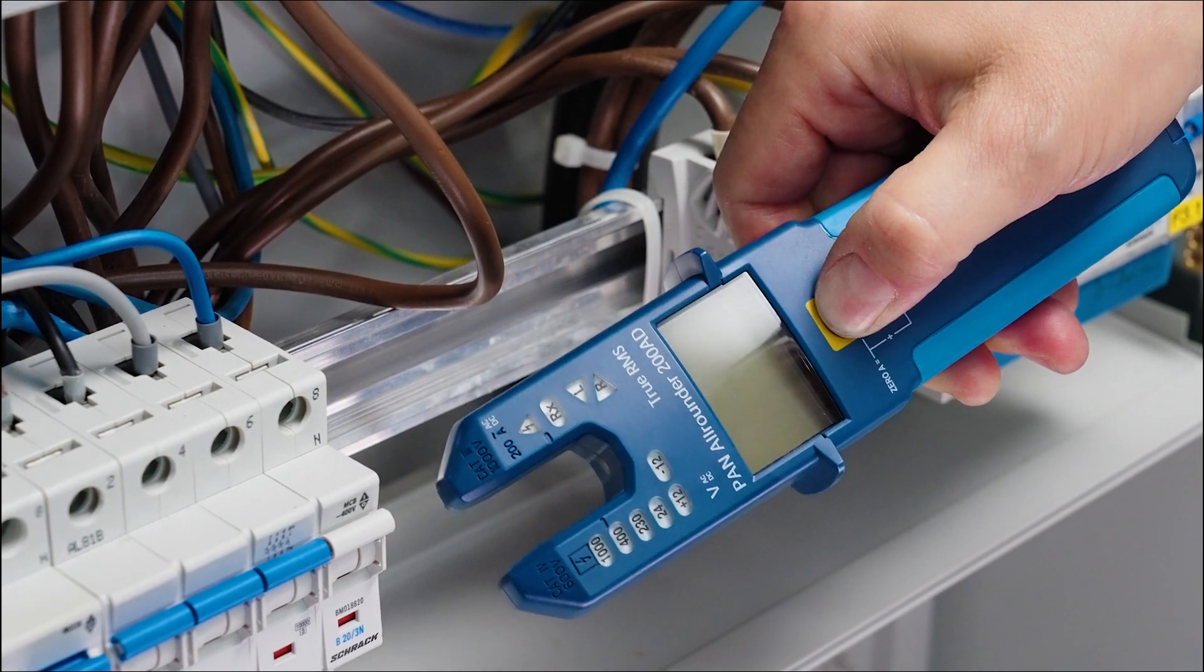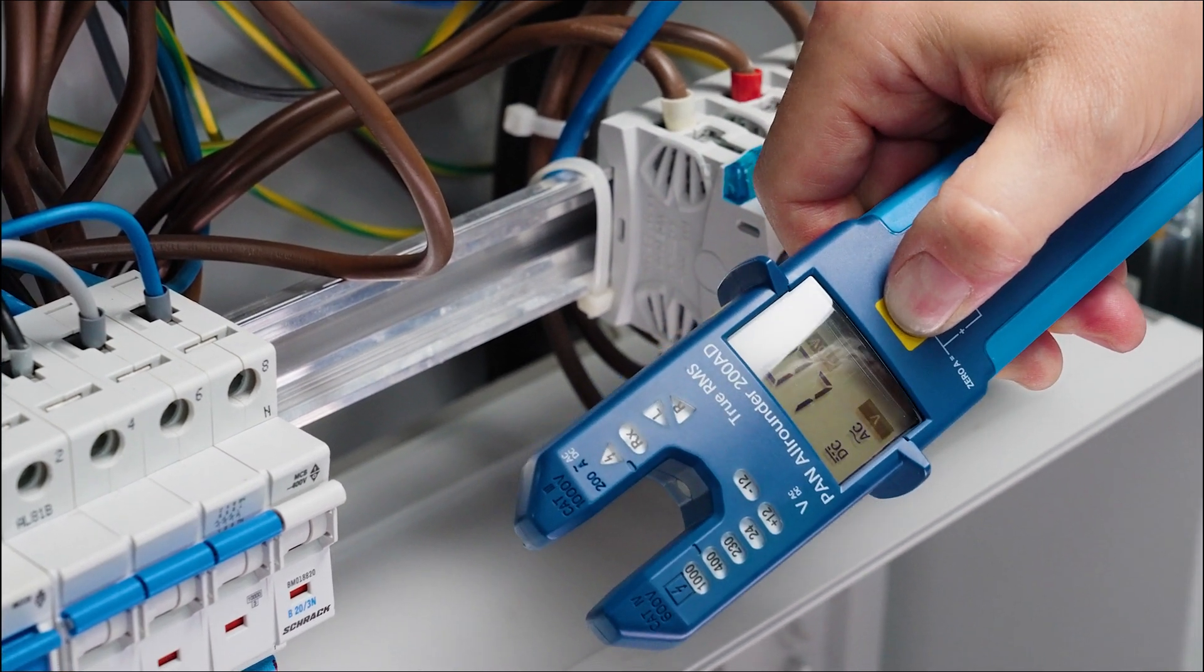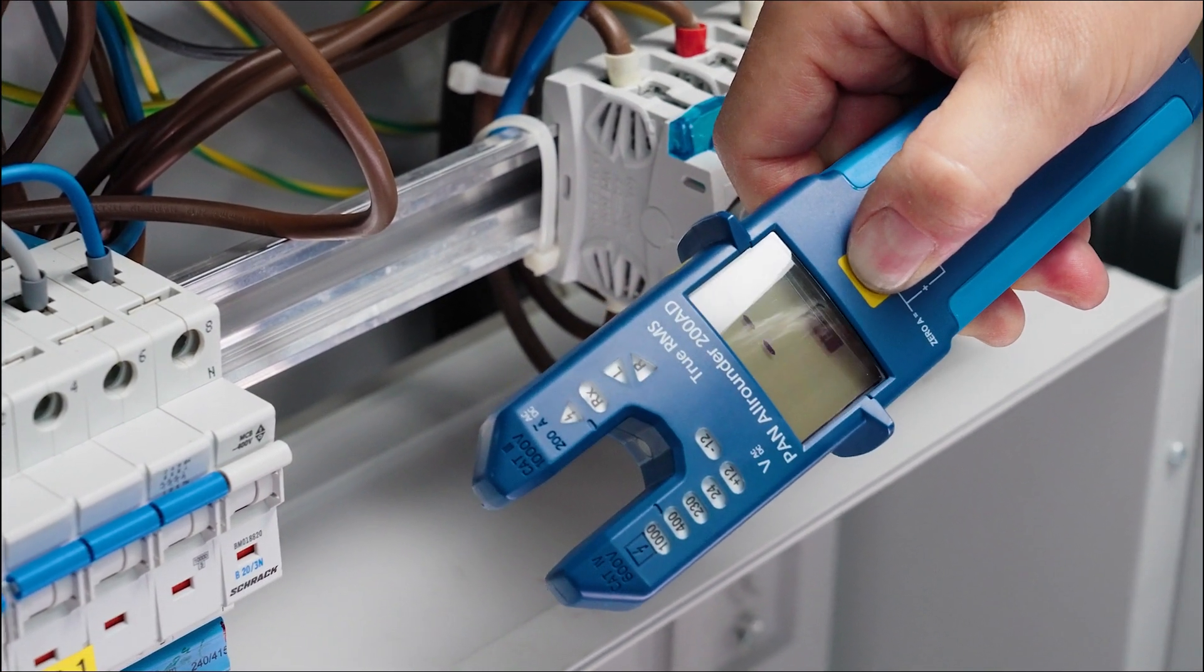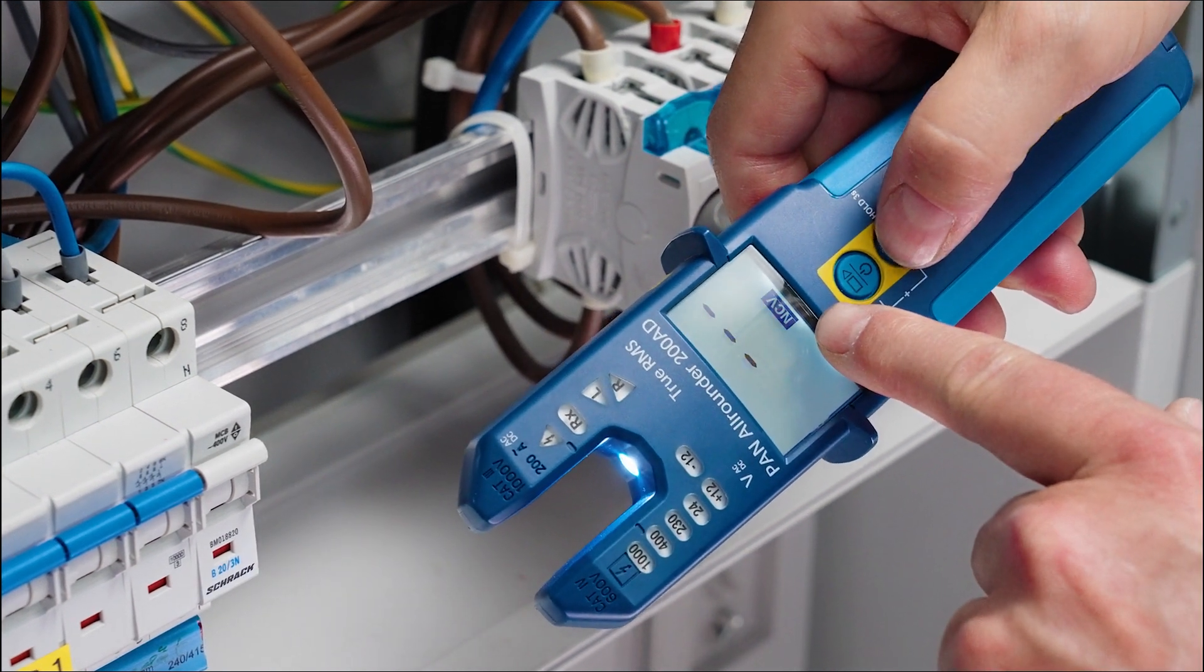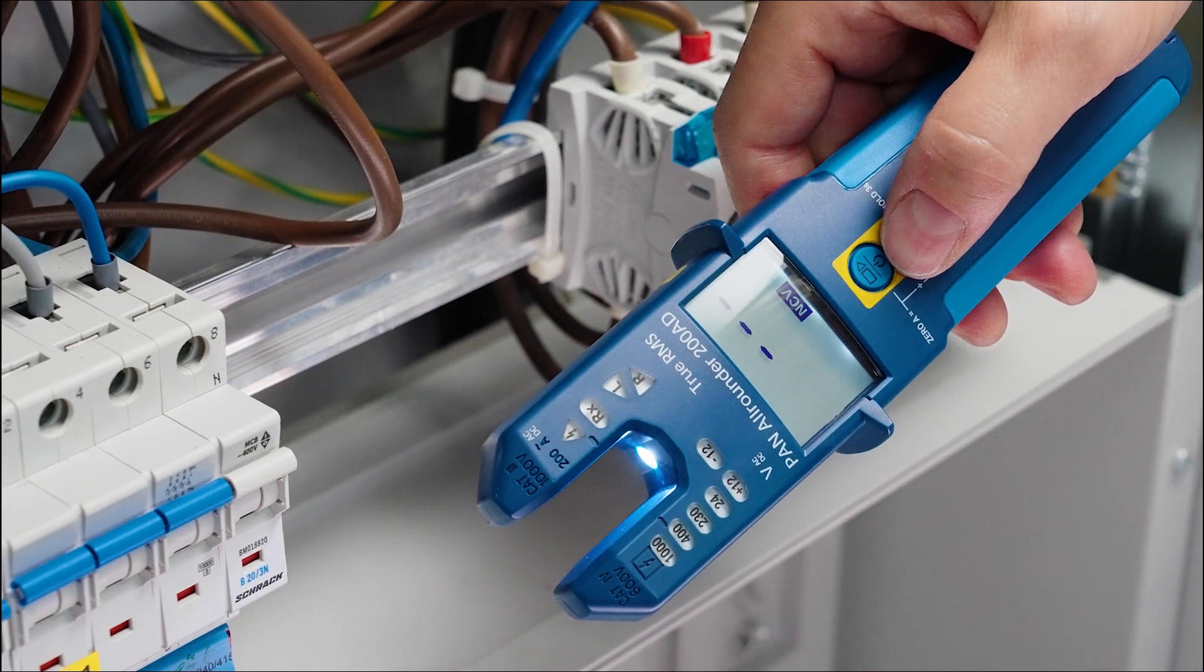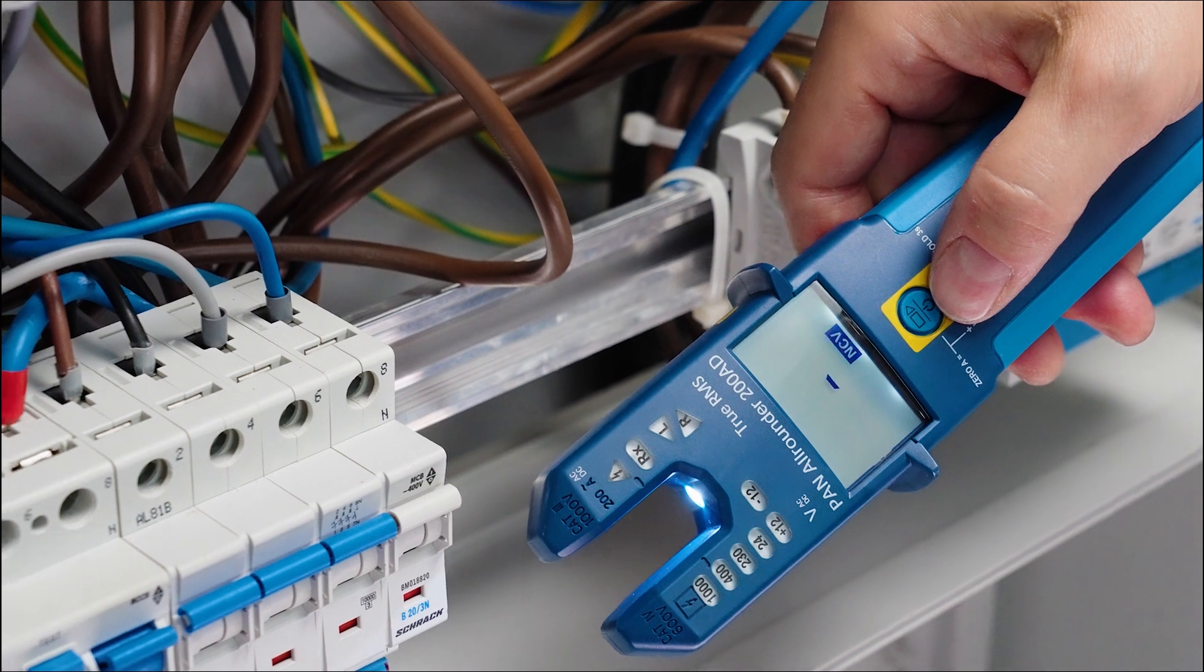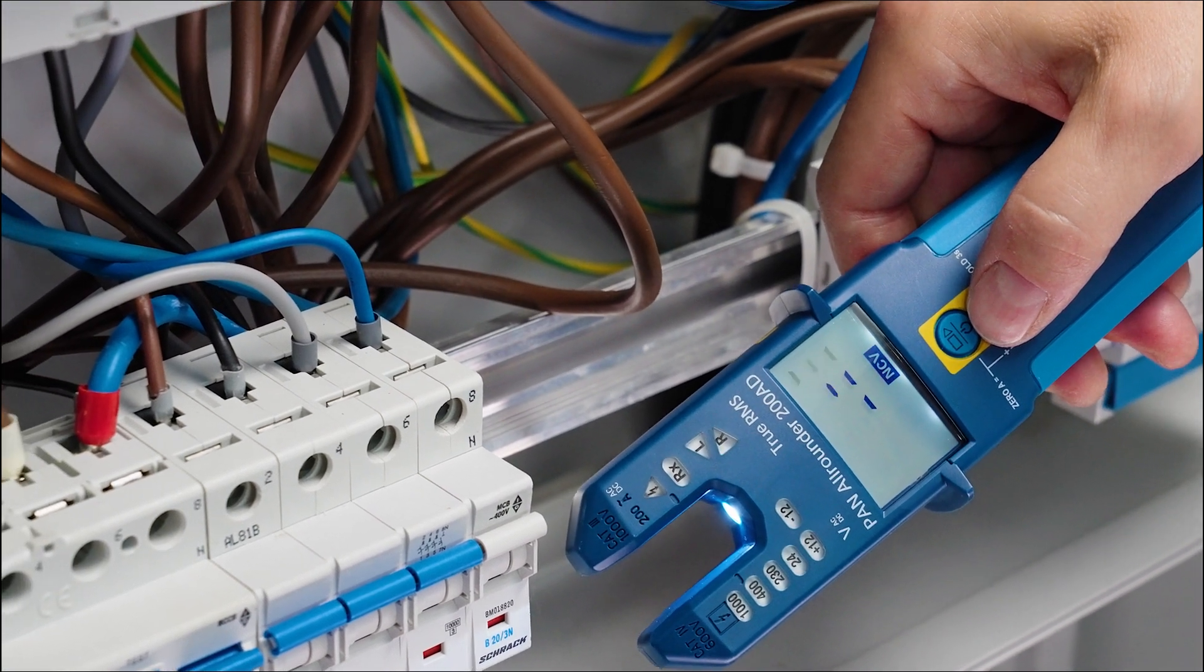To activate this function, we switch the tester on and press the operating button six more times until the display shows NCV for non-contact voltage. When approaching the live conductor, the tester starts beeping and the display shows the strength of the signal in three levels.